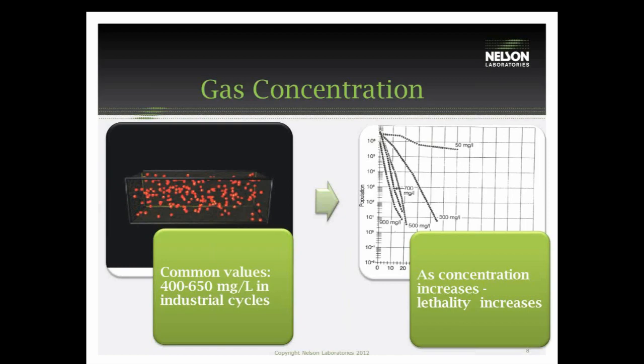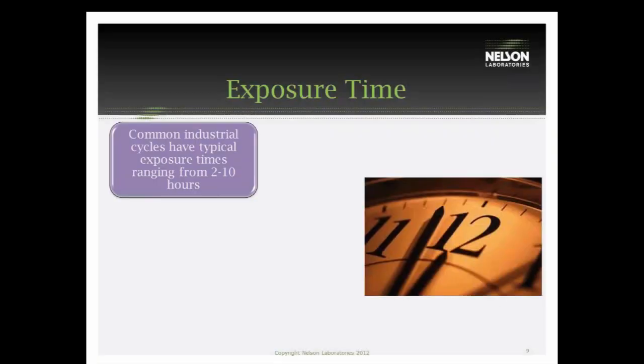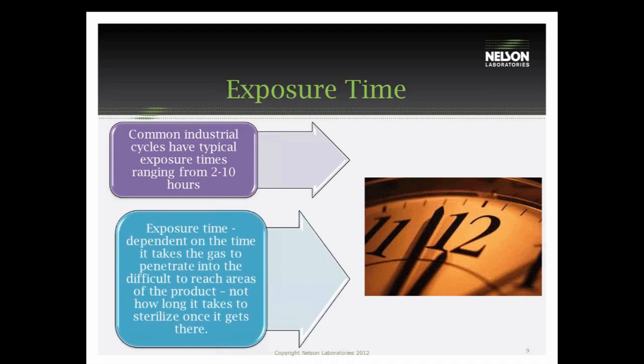It's also important to remember that your gas concentration is going to affect your residual levels, so take note when determining a gas concentration for your cycle. Exposure time: sterilization facilities typically cap that time at about 12 hours. Typical ranges are about 2 to 10 hours of ethylene oxide dwell time. The exposure time really isn't the time it takes for the ethylene oxide to kill the organism, but it's the time it takes for the ethylene oxide to get into the product and get to the locations where the organisms are. So it's not how long it takes to kill it — it's how long it takes to get there.